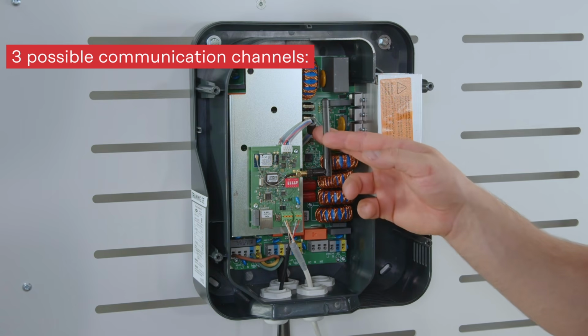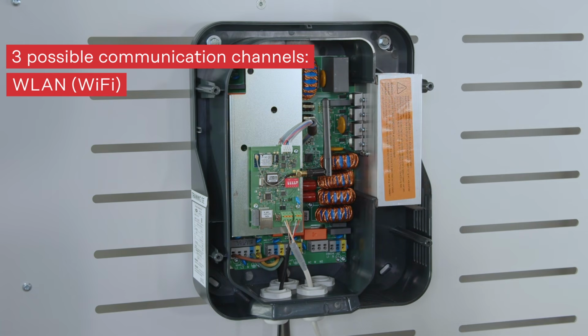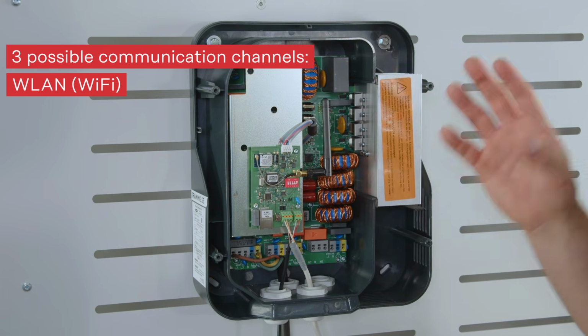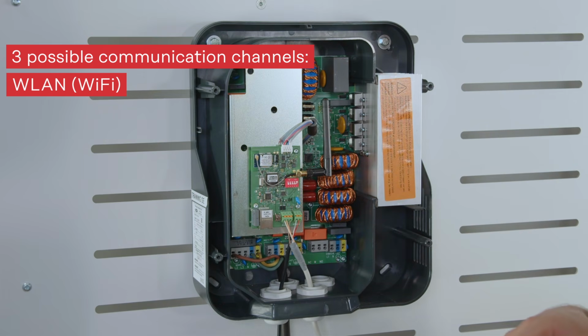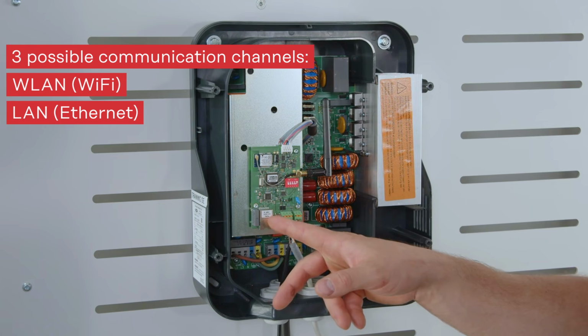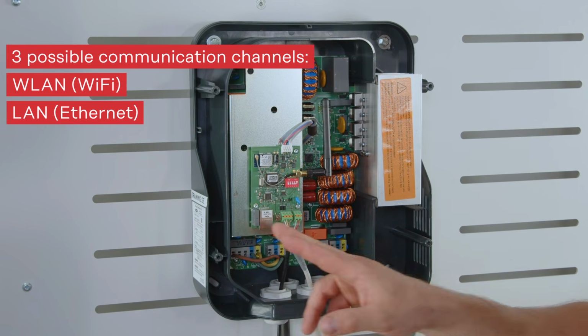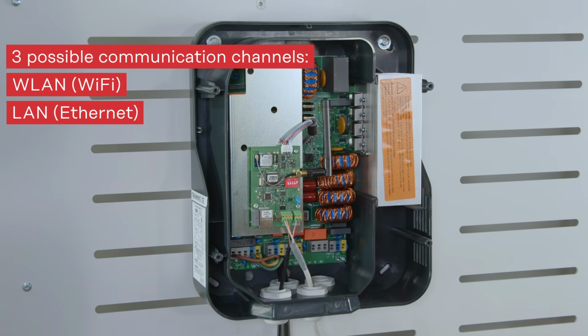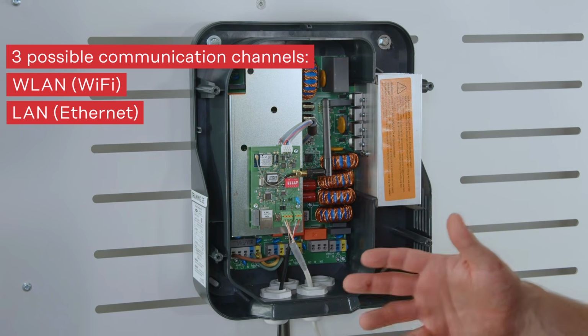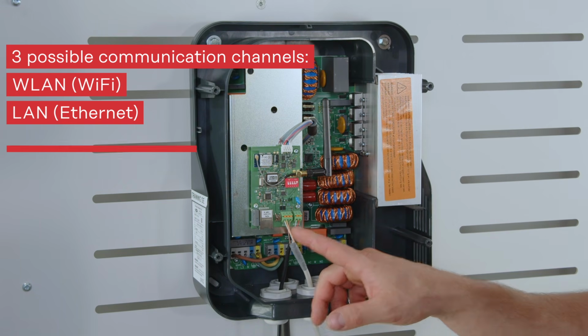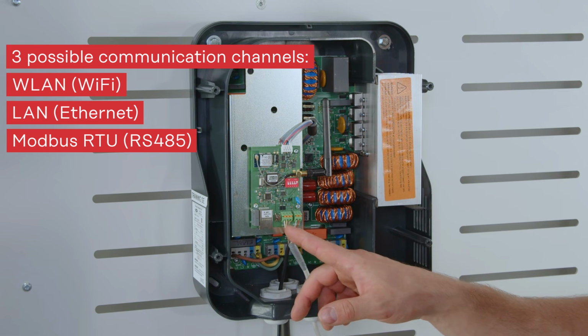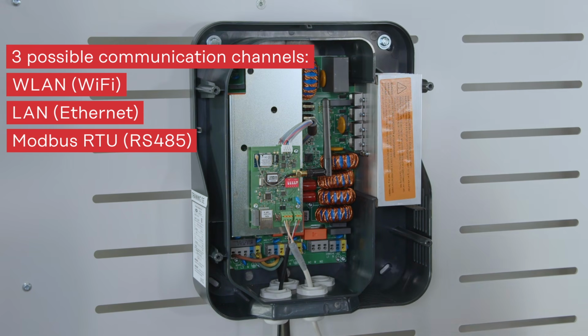So very prominently positioned here we see our Wi-Fi connection or Wi-Fi antenna. So this is possible to connect directly from the Ohmpilot to our network, and via network the Fronius inverter would find the Ohmpilot. The same goes for the network connection. Also here we don't want to go directly to the inverter, but to our network, and over the network connection we then find the Ohmpilot. Or the third option, and also the one that I use today in this setting here, is the Modbus communication. So with this 3-pole connection here, we have the option to use RS485 and directly connect it to the inverter.